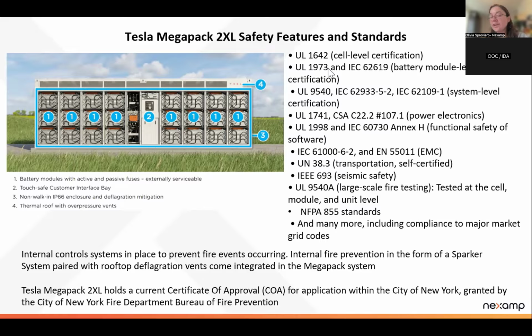The nickel manganese cobalt batteries that are more flammable, they came with dangerous things to breathe in, like acid gases, and they have heavy metals in them. Those I would not say are close to a house or plastics fire. But all these lithium iron phosphate batteries don't have heavy metals in their off-gassing, and it's primarily carbon monoxide. They don't shoot acidic gas out.